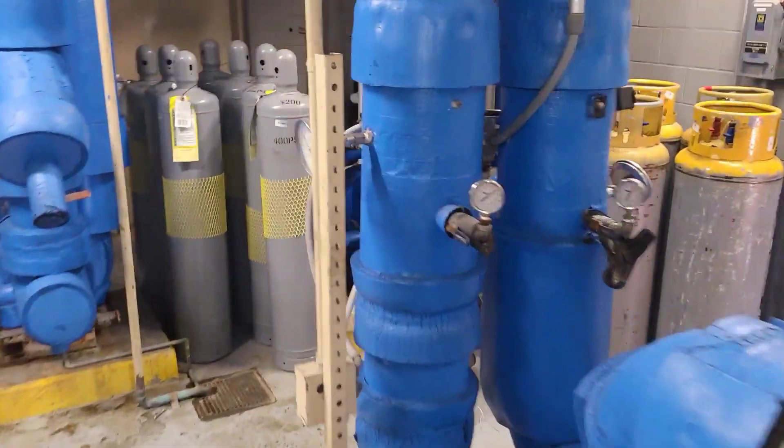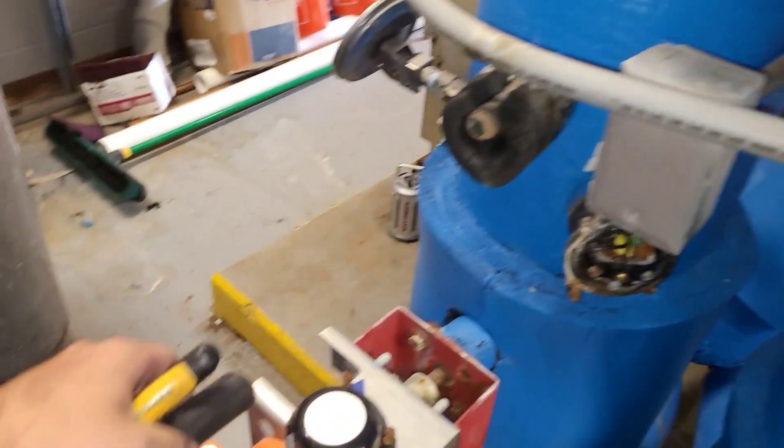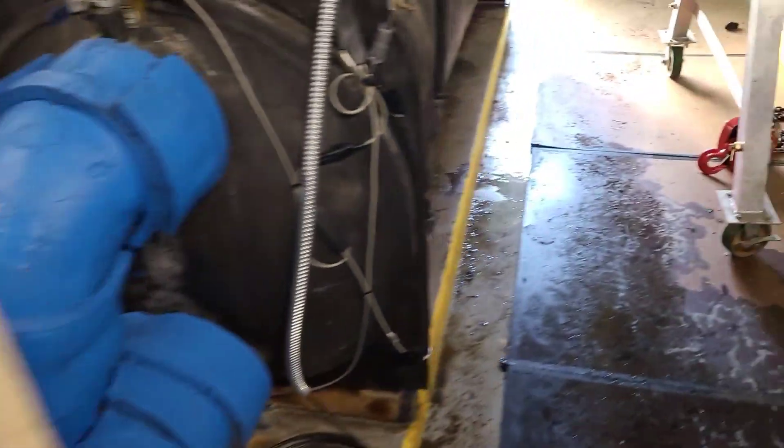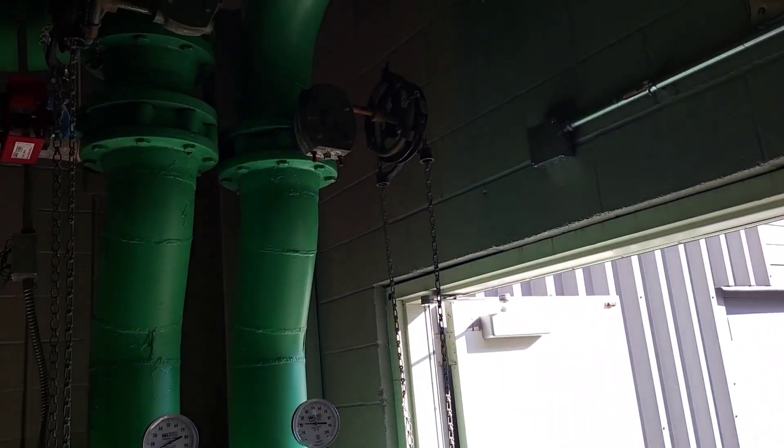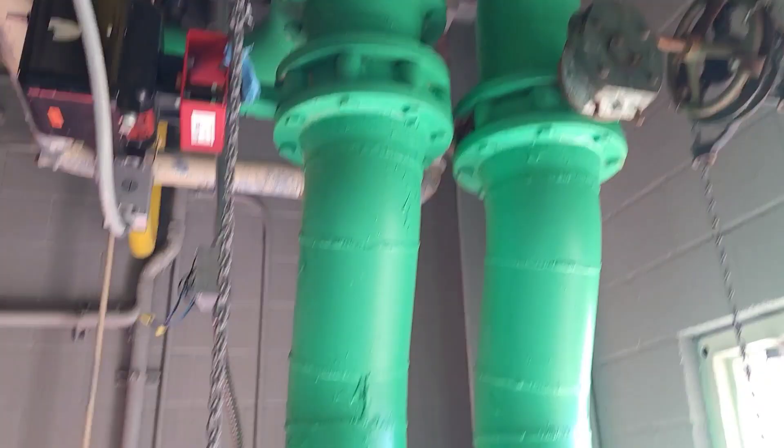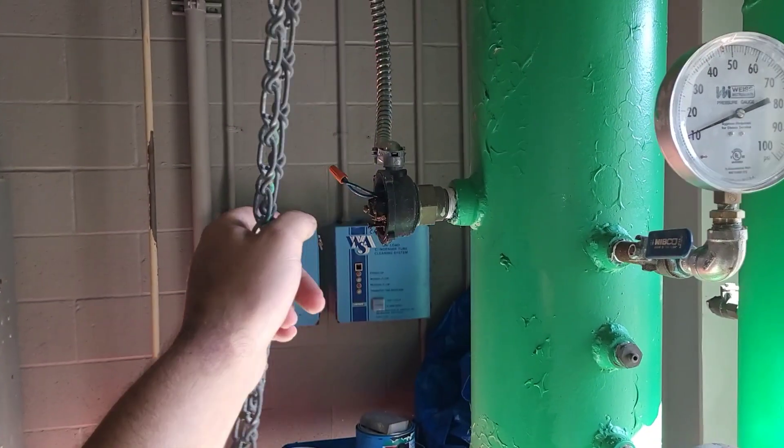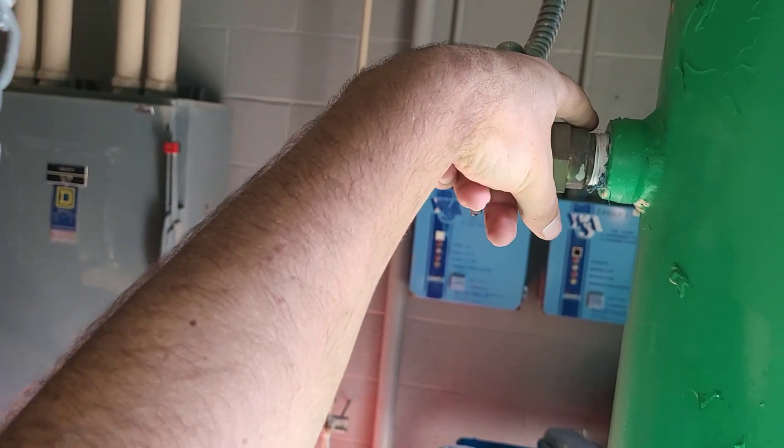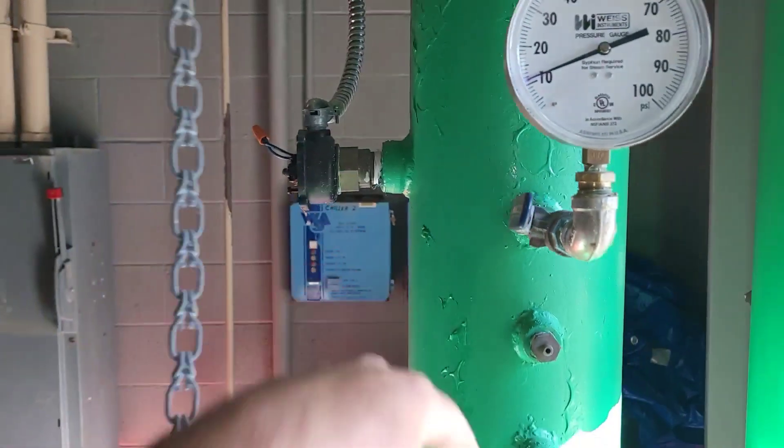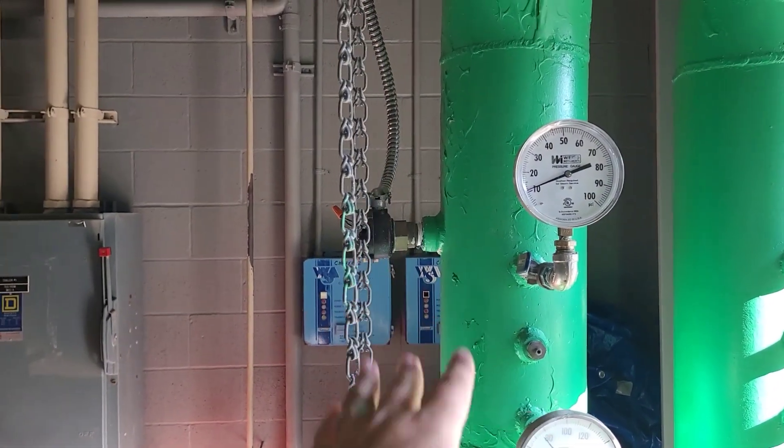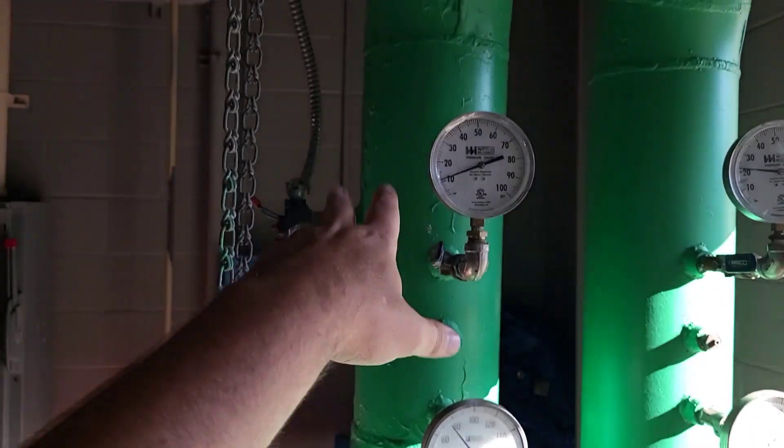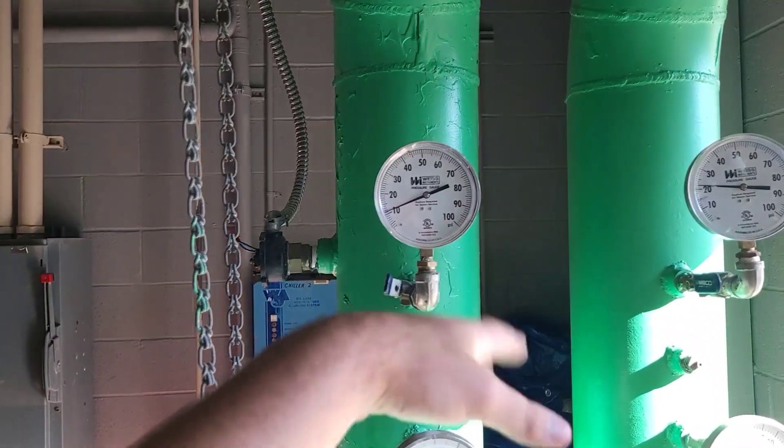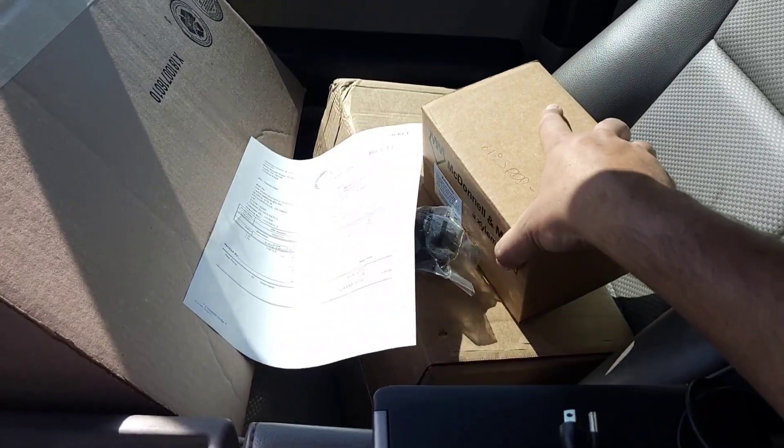From here, I'll go talk to the customer. They should approve a new flow switch. It's not that big of an expense. We will have to come back. We'll isolate the condenser water up there and that'll allow us to pull this flow switch out, drop a new one in. That is a one inch nipple, so we'll just need to make sure that whenever we get the new one to get a one inch size. It won't take long to do the change out. All it is just a set of paddles in there. Not that big a deal.